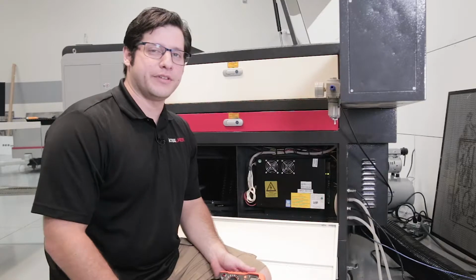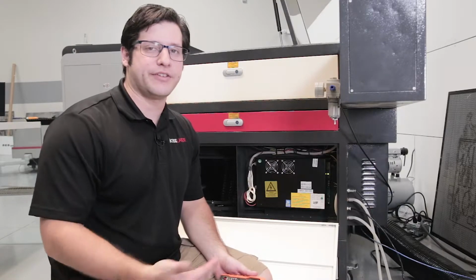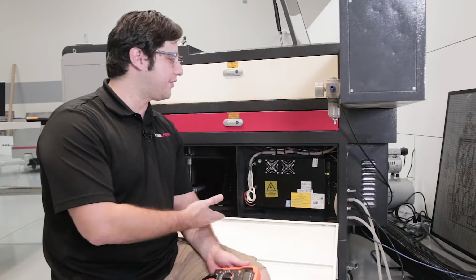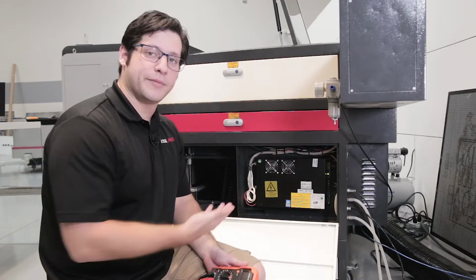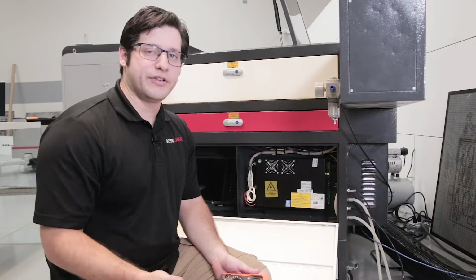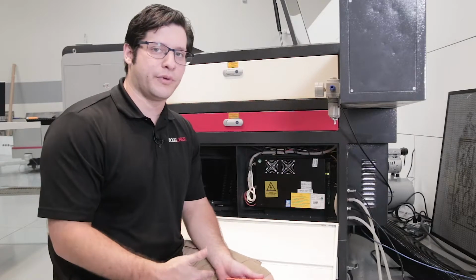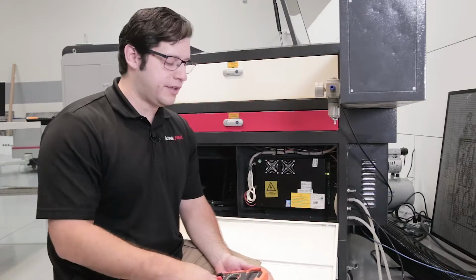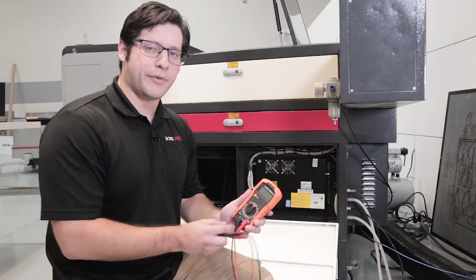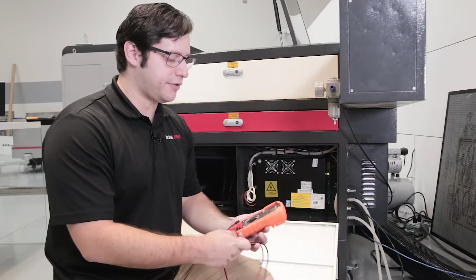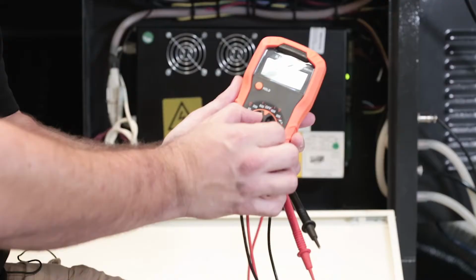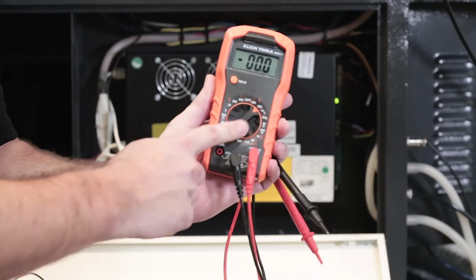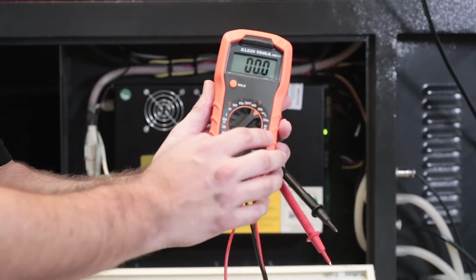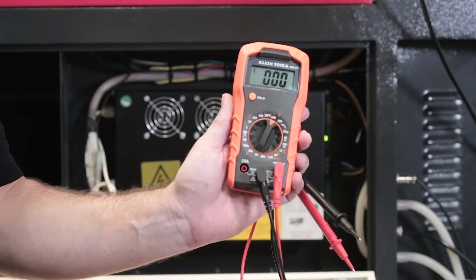The first step that you want to do when checking for your interlocks is to actually make sure that you're getting power to your laser power supply. It's going to be located on the right side of your machine, on the biggest cabinet here. When you check it, you're going to be checking for 120 volts, or if your system's set up for 220, you want to check it like that. So you'll get your multimeter and change it over. It's going to be AC voltage. For 120, you're going to have it at 200. For 220, you're going to have it at 600.